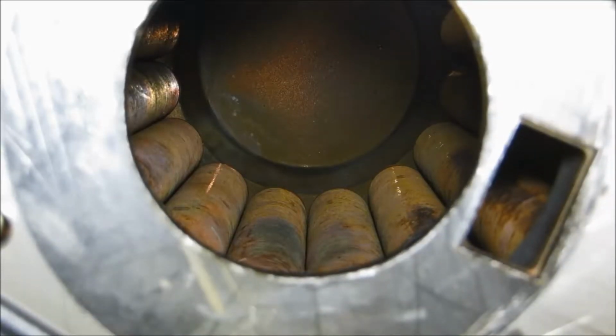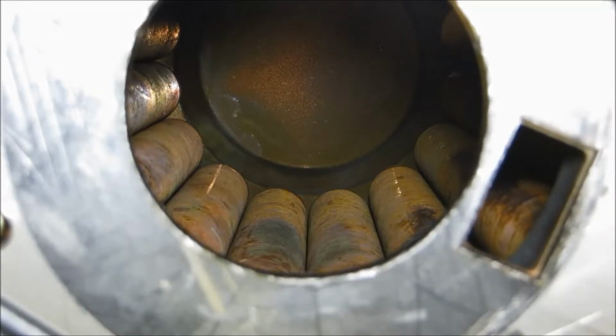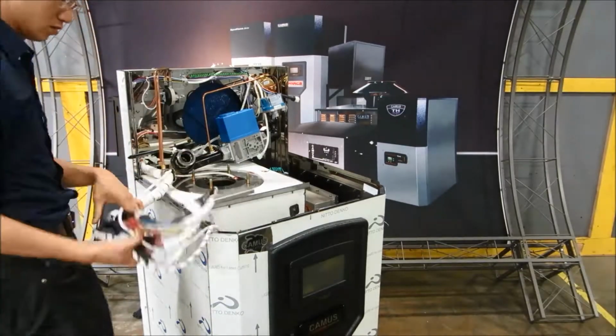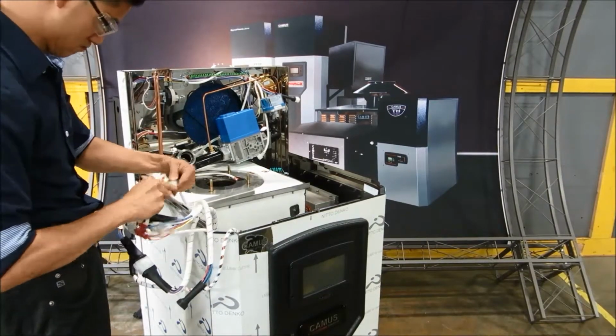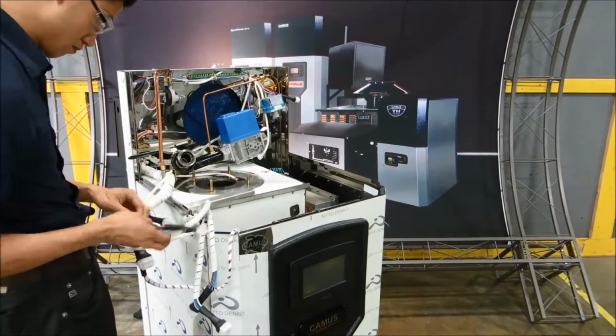With the burner removed, you can now inspect the condition of the copper or stainless steel water tubes. This particular heat exchanger looks clean. If there is buildup of sediment on the tube, this will need to be cleaned using a pressure washer, which will be detailed later in the video. Unplug the wiring harness so that the control box harness is detached from the boiler harness.